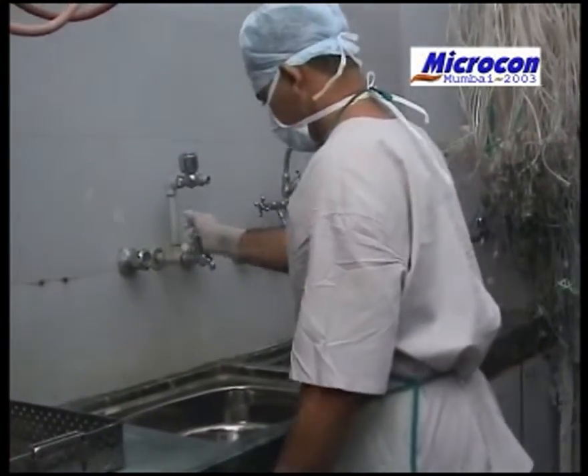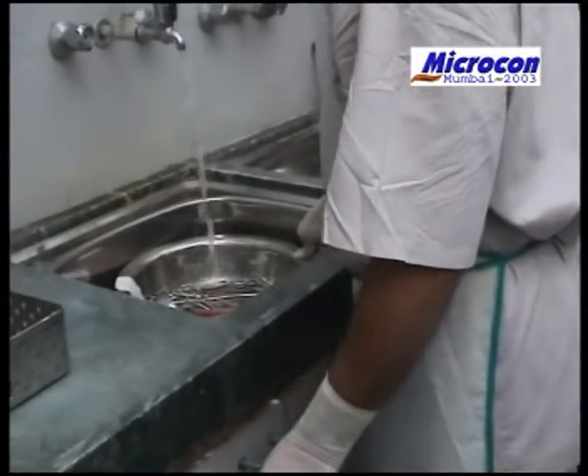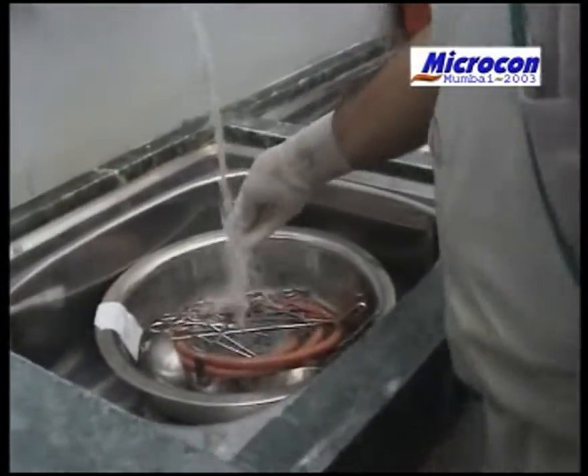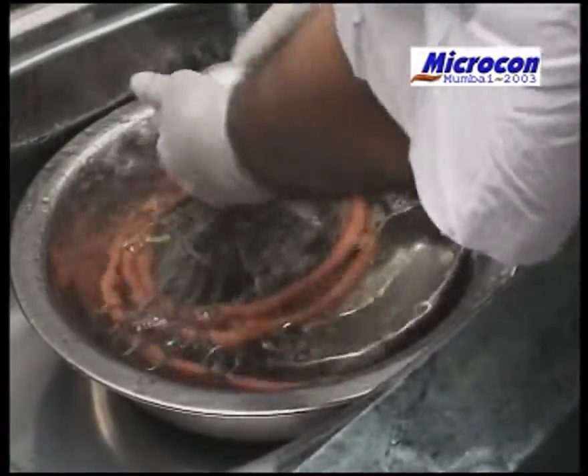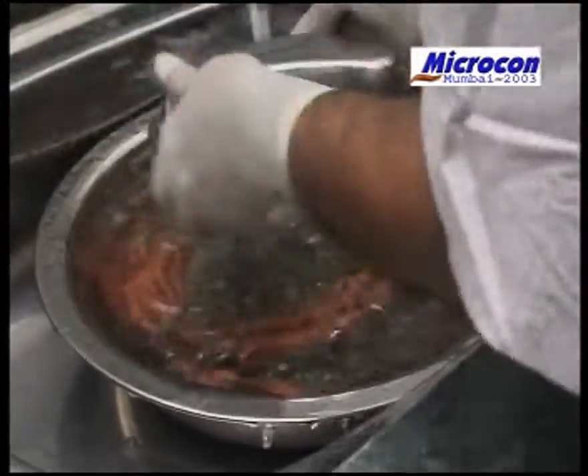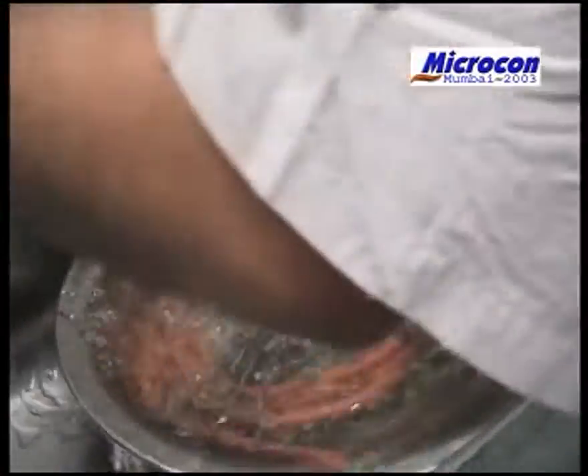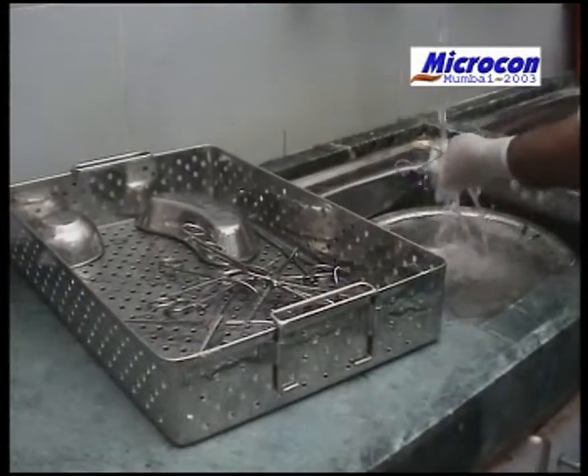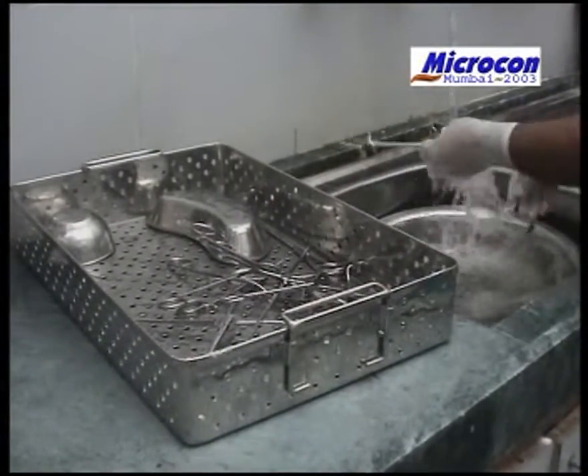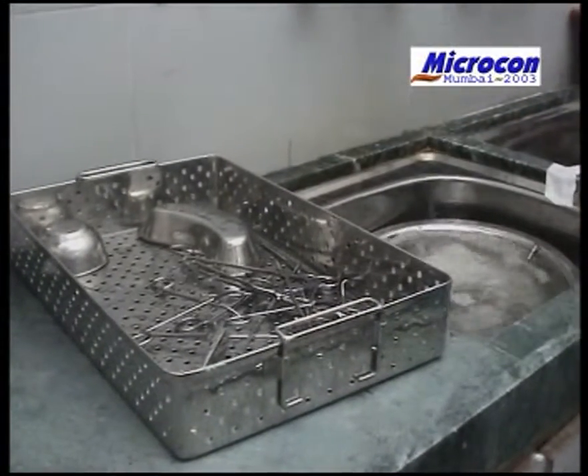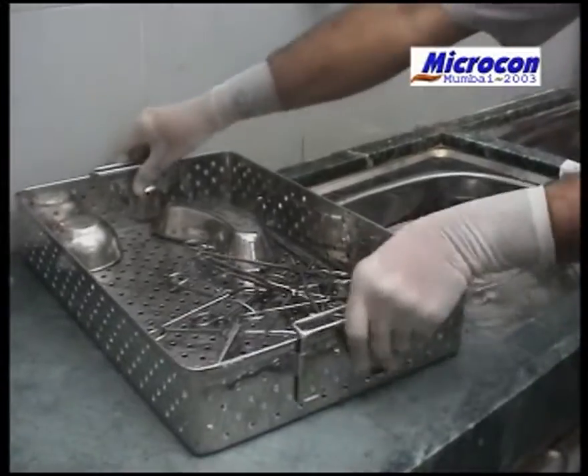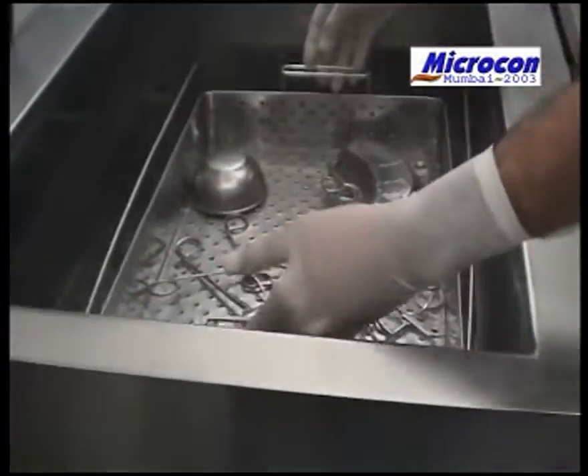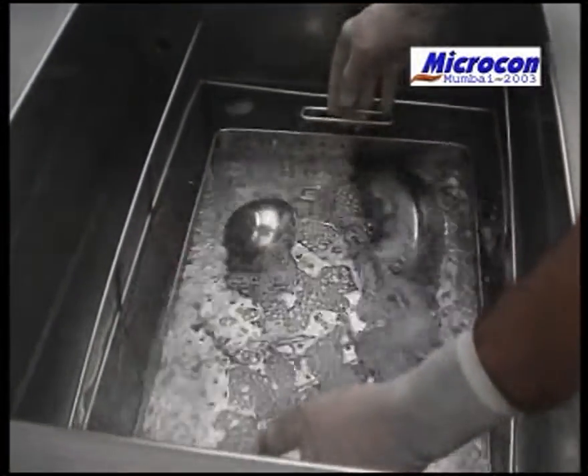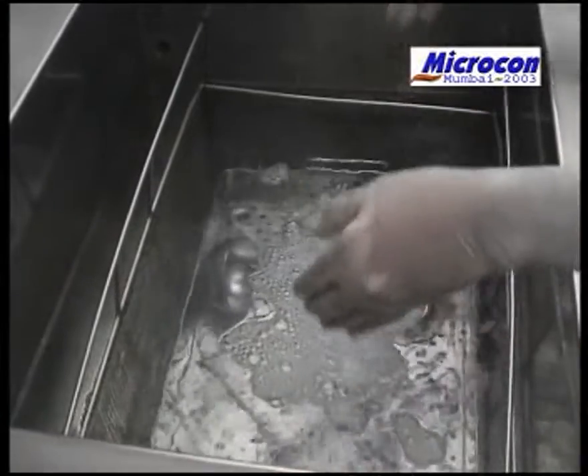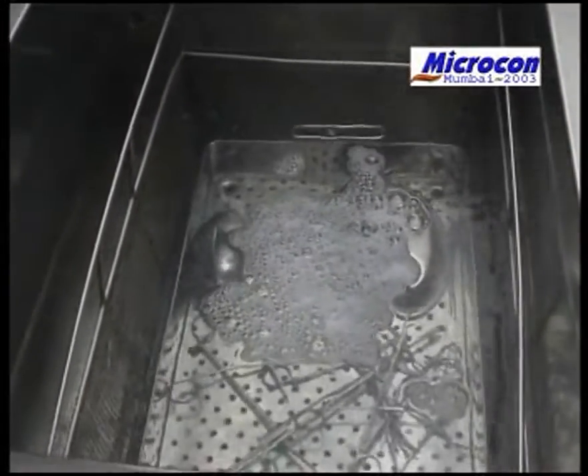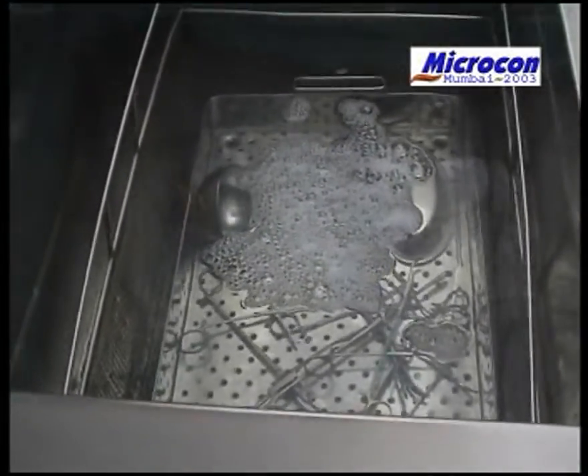The soiled instruments which are delivered to the sterilization or CSSD department begin with washing. The washing process today is crucial to the process of sterilization because mechanical cleaning of an instrument reduces the bioburden from 10 raised to 5 microorganisms to 10 raised to 2 microorganisms. This highlights why and how this step is critical.